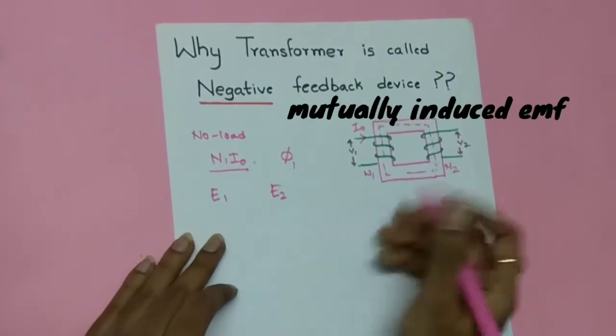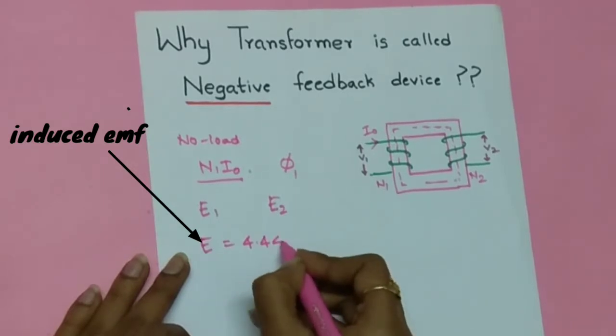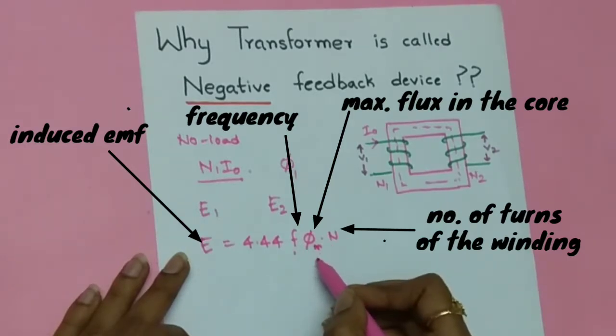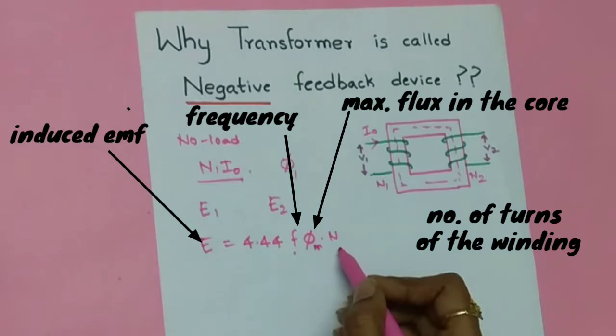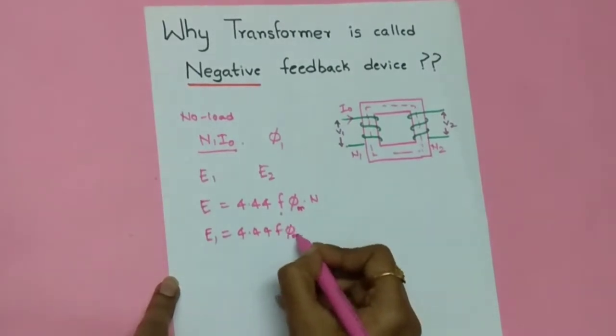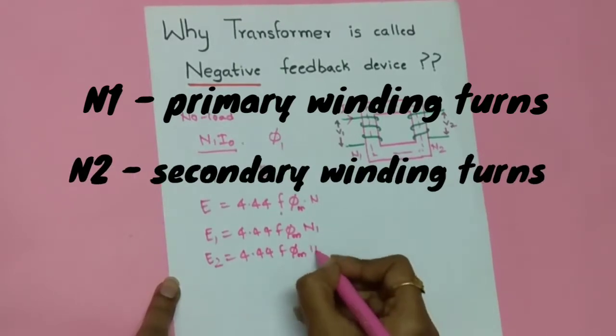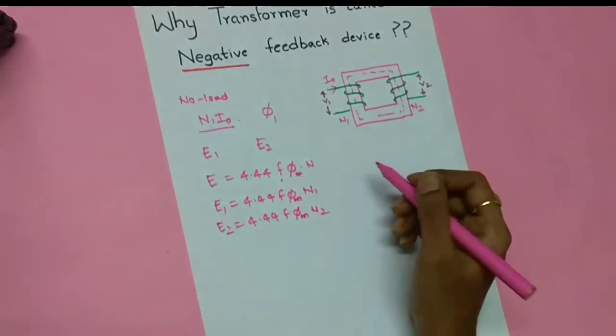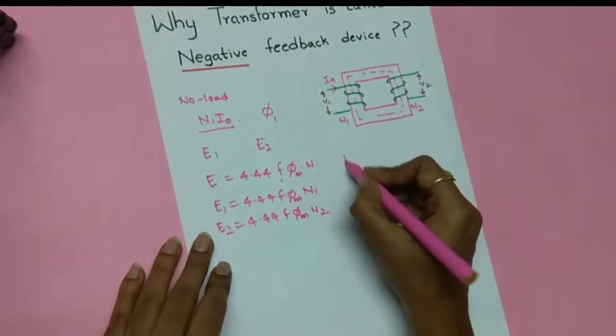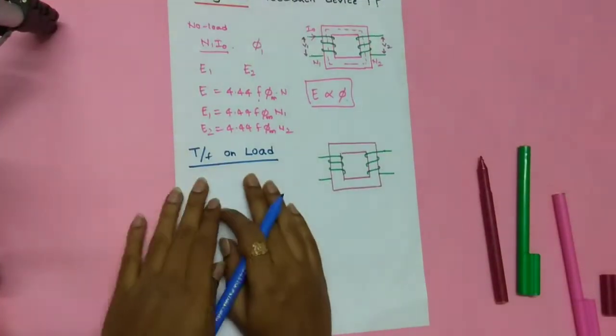Since this flux links with both the primary and secondary windings, an EMF e2 is also produced in the secondary winding. The formula is: e = 4.44 × f × φm × N, where f is frequency, φm is maximum flux, and N is number of turns. So e1 = 4.44·f·φm·N1 and e2 = 4.44·f·φm·N2. For a fixed frequency and fixed turns, the EMF e is directly proportional to the flux.